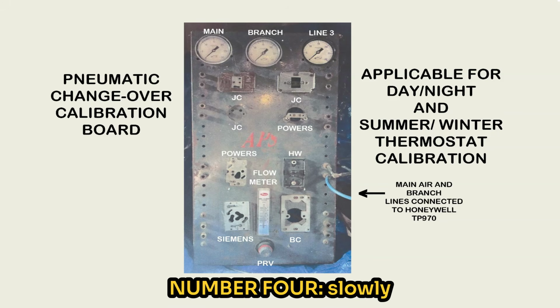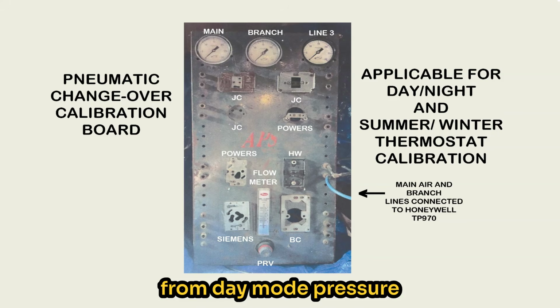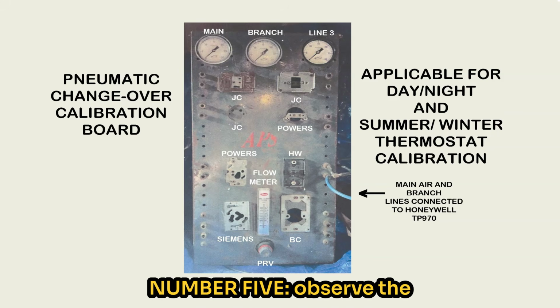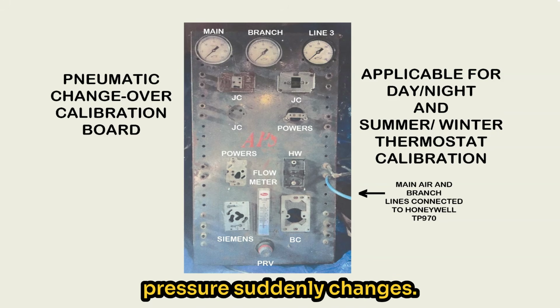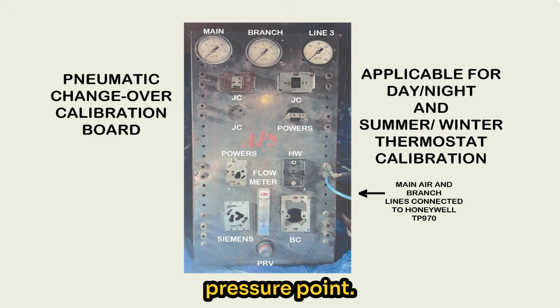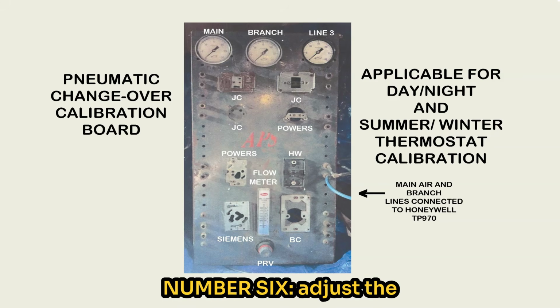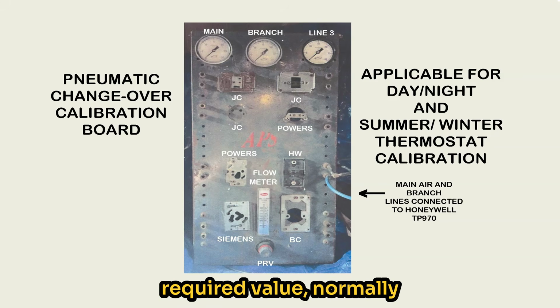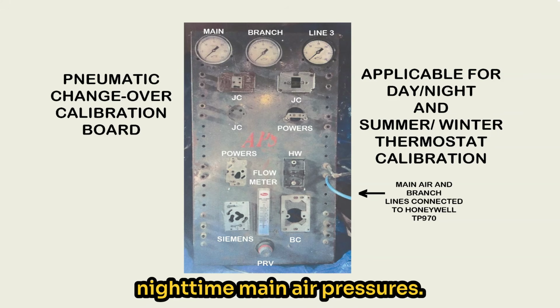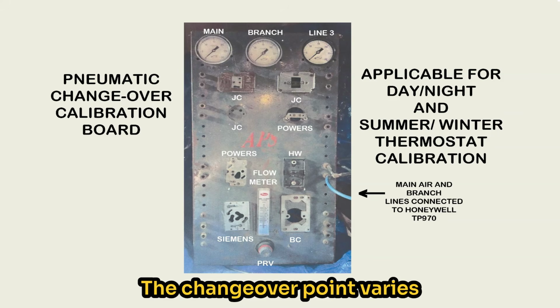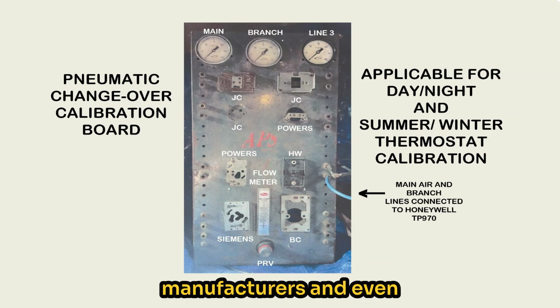Number 4. Slowly increase the main air pressure from day mode pressure toward night mode pressure. Number 5. Observe the point at which the branch pressure suddenly changes. This is the changeover pressure point. Number 6. Adjust the changeover pressure to the required value, normally approximately midway between the established day and nighttime main air pressures. The changeover point varies considerably between manufacturers and even between models from the same manufacturer. However, the changeover function can generally be tested and calibrated. The method of calibration varies with models.